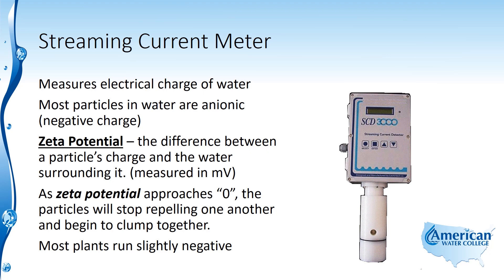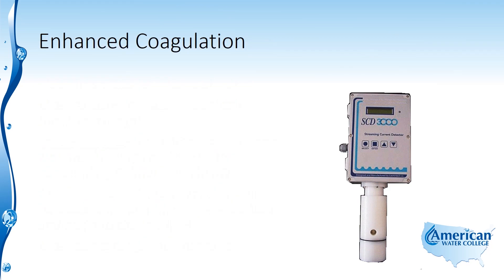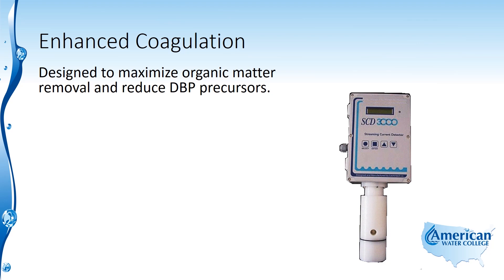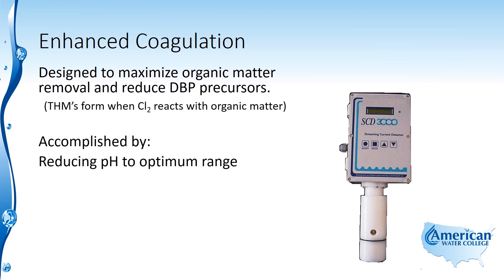Most plants run slightly negative, and that's because you don't want to overdose your coagulant, because that can cause water quality issues in the distribution system. Another way to operate the coagulation process is what's called enhanced coagulation, and that's designed to maximize organic matter removal and to reduce disinfection byproduct precursors — specifically trihalomethanes — because trihalomethanes form when chlorine reacts with organic matter in the water.